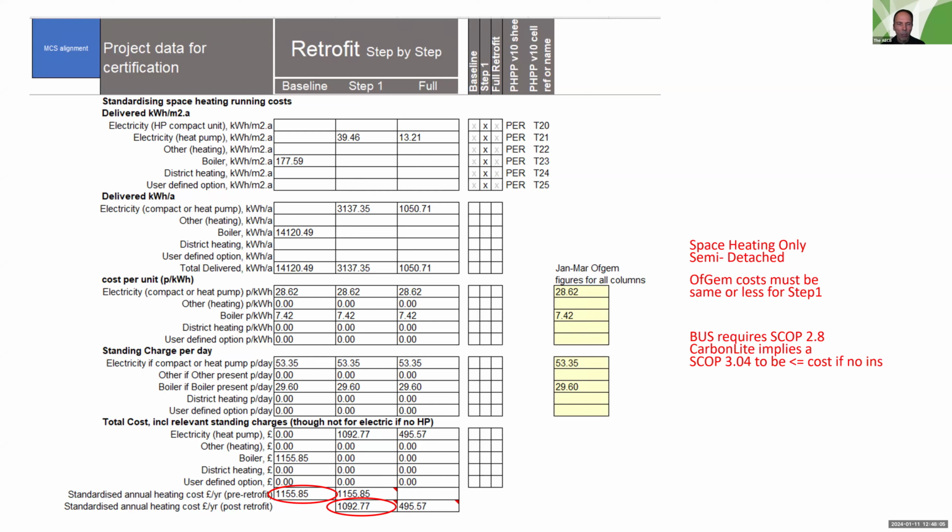You can get very rough figures from the manufacturer, but they don't know where in the country it's going to be. So they don't really know what climate it's going to be installed in. So it makes a lot of difference by modeling the actual building, the actual heat pump, the actual climate. And that's what PHPP does really well. And that's a really good base point to start with.